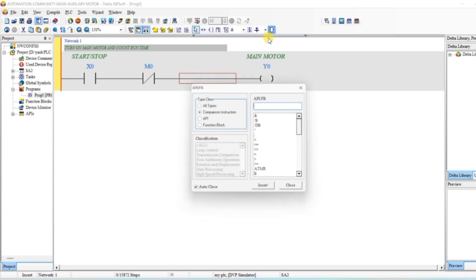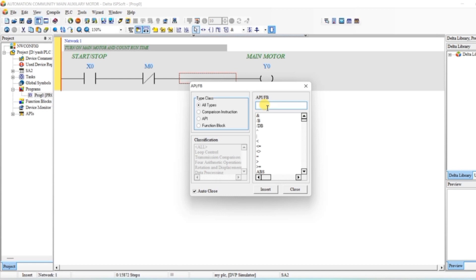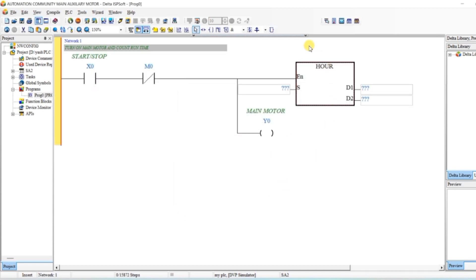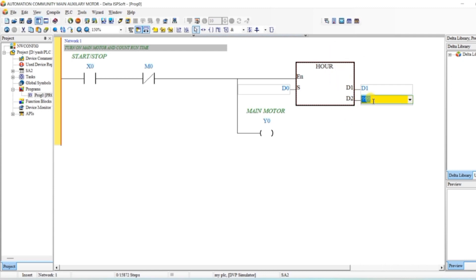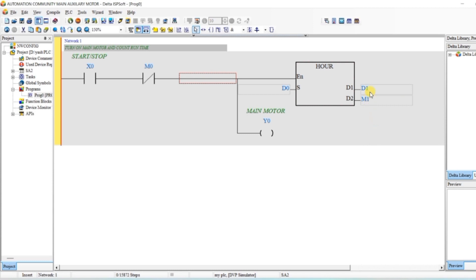Now go to the function blocks, select all types, type HOUR and click Insert. The HOUR block is inserted. Here we want to get the set value from the user via HMI, so we use data register D0 as the set time. D1 is our run time data register. The output here — which the help calls D2 — is not a data register; it is just indicating the output, for which I will write M1. When both values become equal, M1 will turn on. Similarly, we will write the same code for the auxiliary motor.